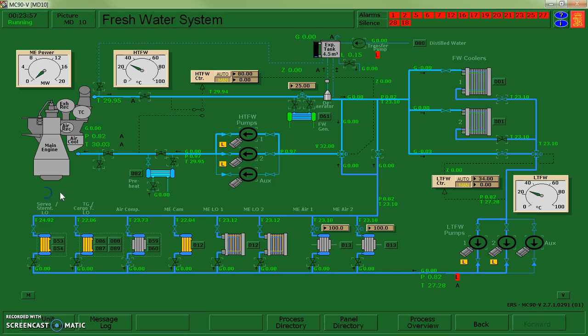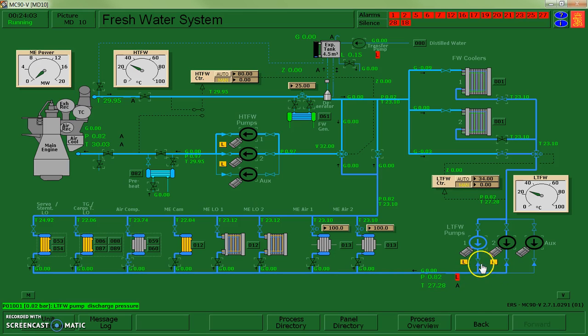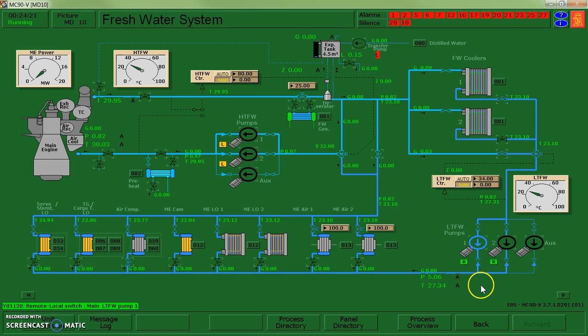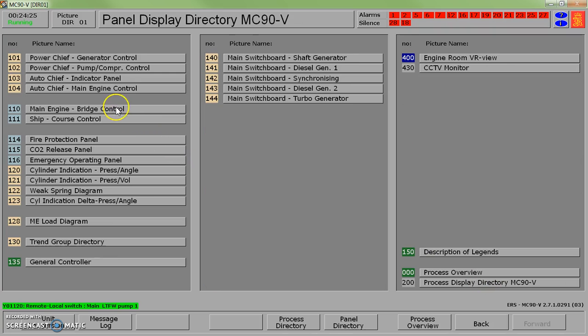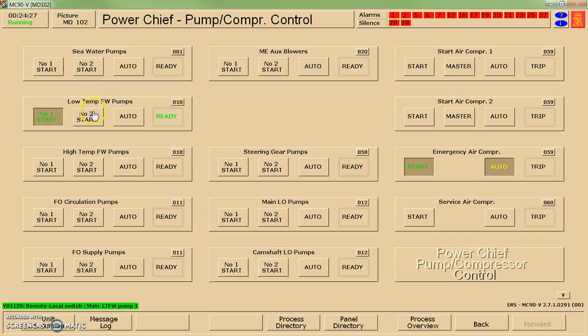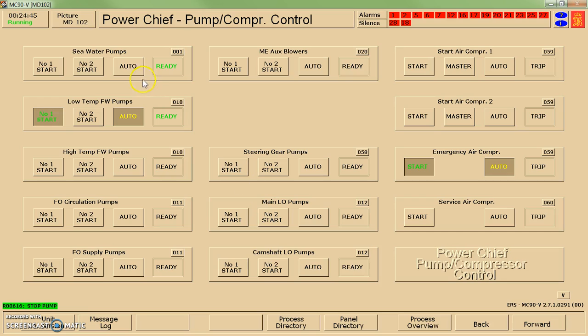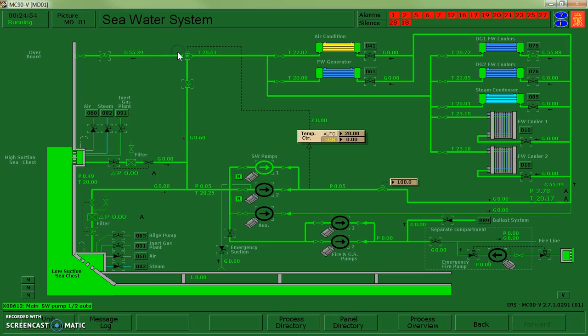Let's go to our fresh water system. Now that we have these pumps active, we should be able to turn them on. If it's not in the right mode, local or remote, it won't let you start. Right now I'm local and I can activate them here. I'm going to switch them up to remote and just like we had on page four compressor control, I'm going to switch these guys over to auto. I'm going to do the same thing over here at number one - switch these guys to remote control, turn off my auxiliary pump, and turn these guys into auto mode. Confirm that they're going to turn themselves off, and we do have a pump that's on.